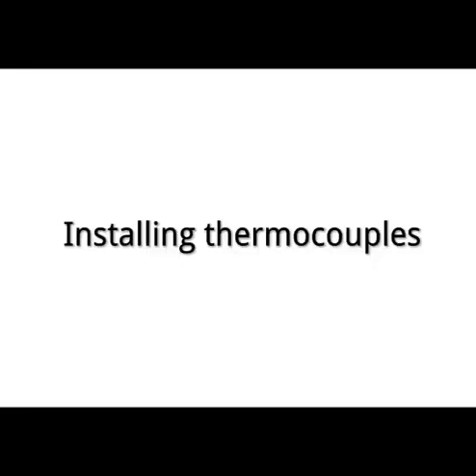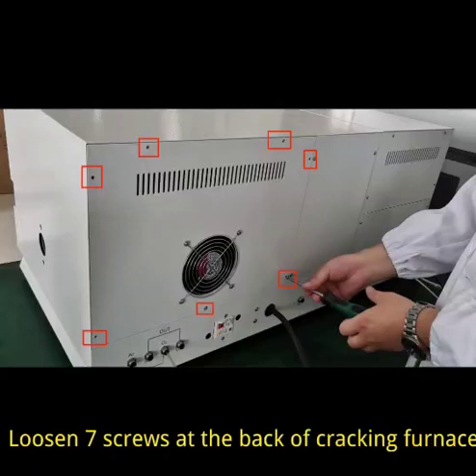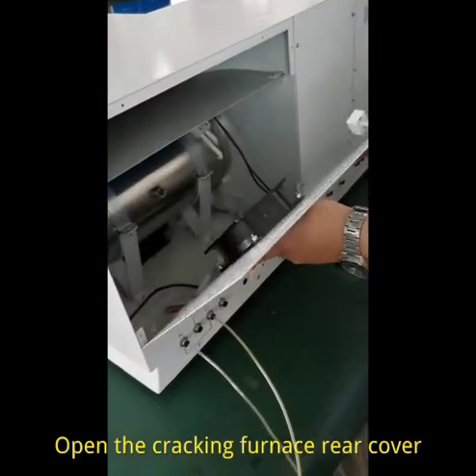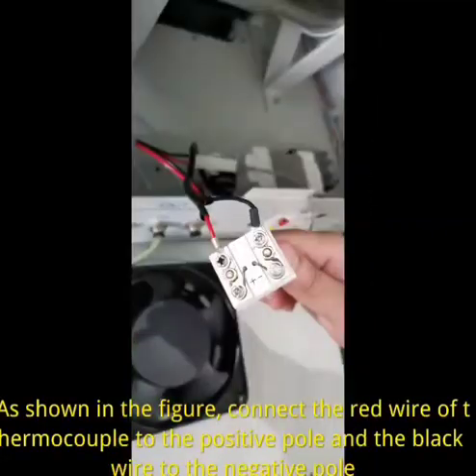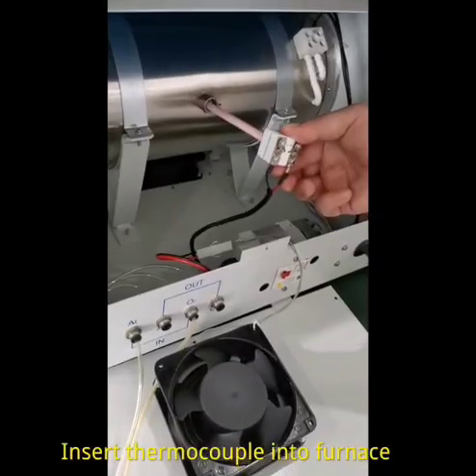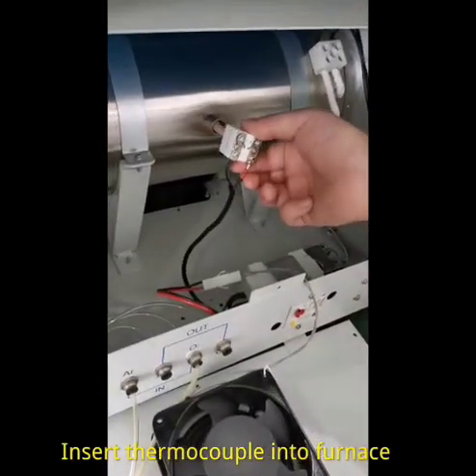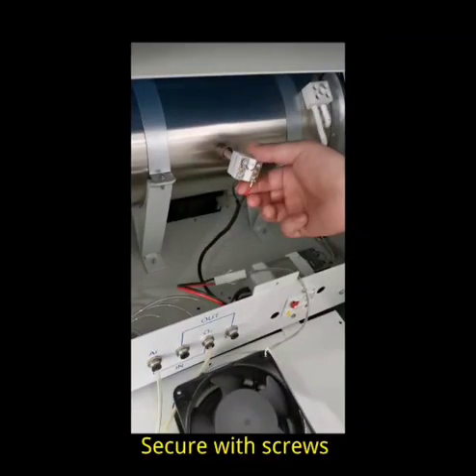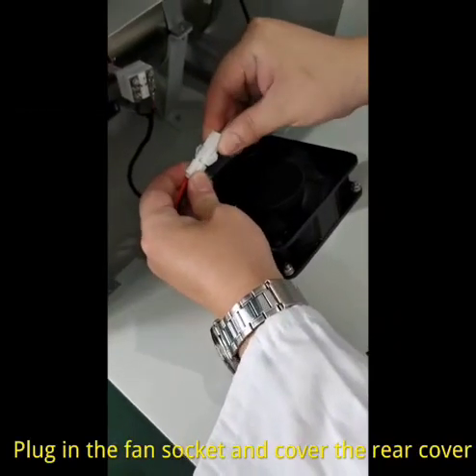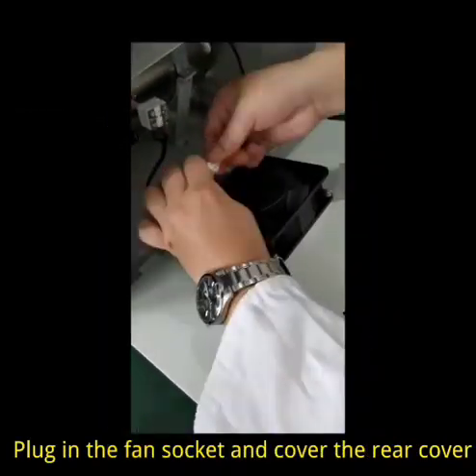Installing thermocouples. Loosen 7 screws at the back of the cracking furnace. Open the cracking furnace rear cover. As shown in the figure, connect the red wire of the thermocouple to the positive pole and the black wire to the negative pole. Insert the thermocouple into the furnace. Secure with screws. Viewed from the furnace mouth, the thermocouple just shows the top. Plug in the fan socket and cover the rear cover.